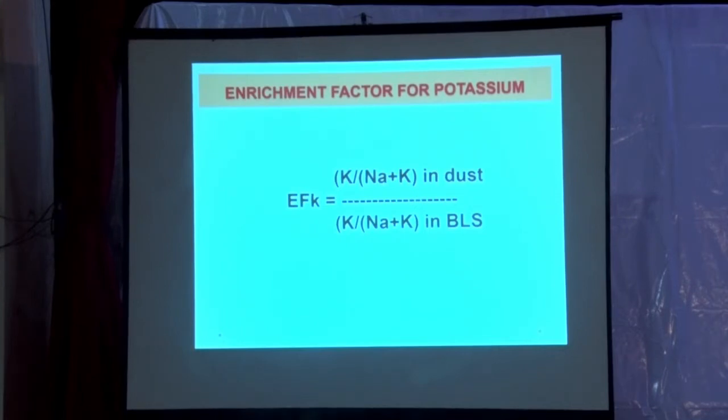So a term has been developed to bring all mills to a common level; they termed it the enrichment factor. In ESPs, don't measure the NaCl, measure the enrichment factor of potassium and the enrichment factor of chloride, so that you can fix a limit. If my enrichment factor is this, I can control it, and I can have maximum benefits of my recovery boiler as far as thermal and chemical recovery is concerned.